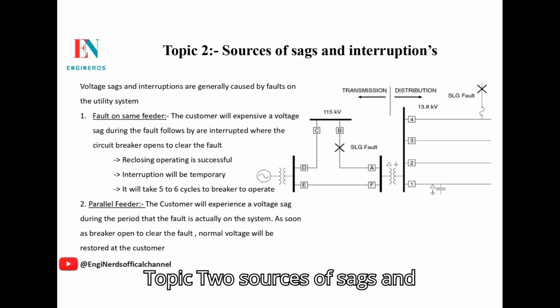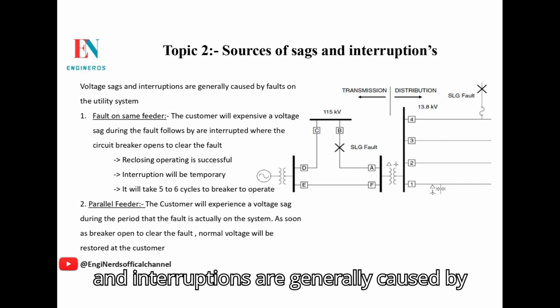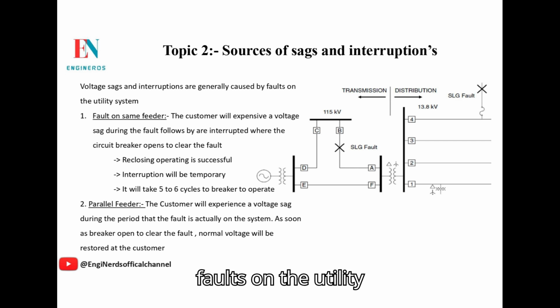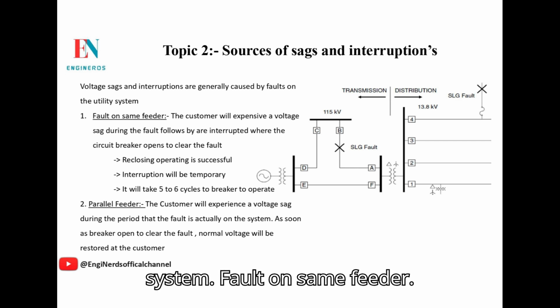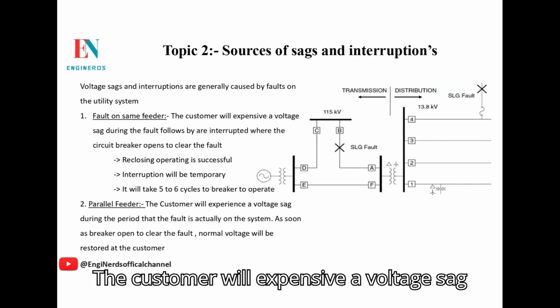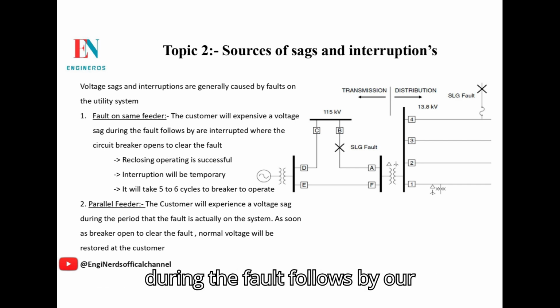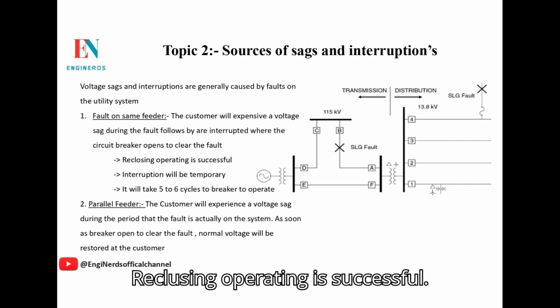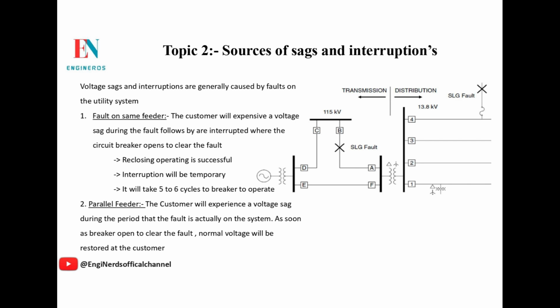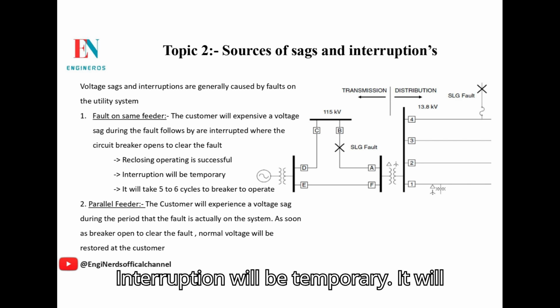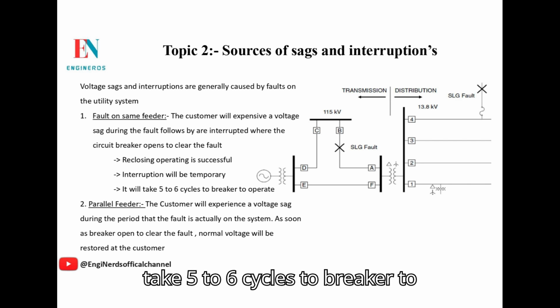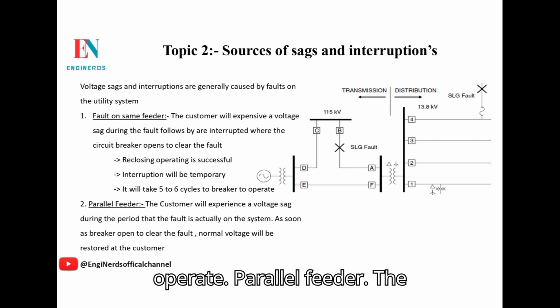Topic 2: Sources of sags and interruptions. Voltage sags and interruptions are generally caused by faults on the utility system. For a fault on the same feeder, the customer will experience a voltage sag during the fault, followed by an interruption when the circuit breaker opens to clear the fault. If reclosing is successful, the interruption will be temporary. It will take 5 to 6 cycles for the breaker to operate.